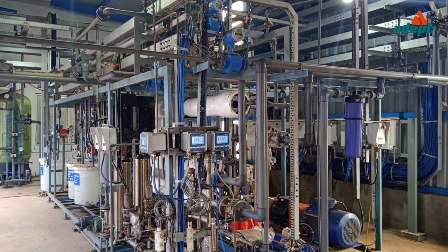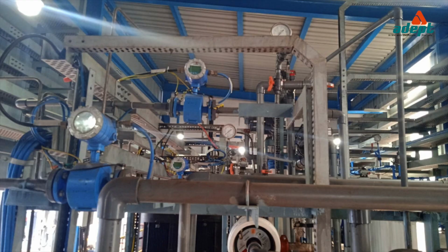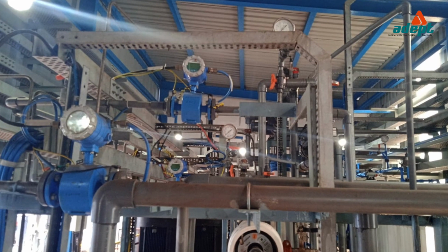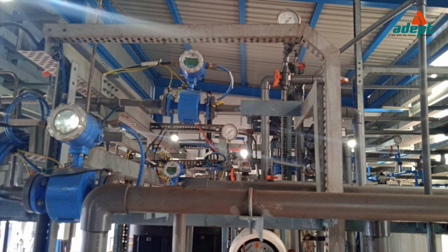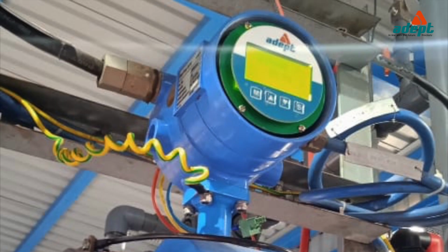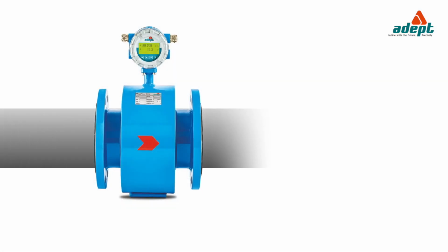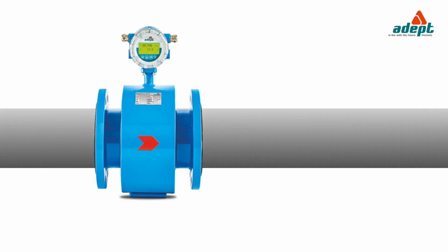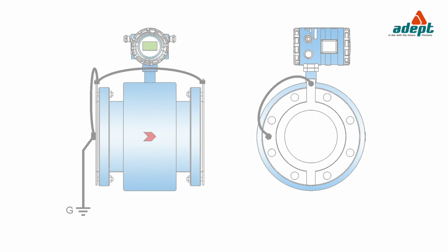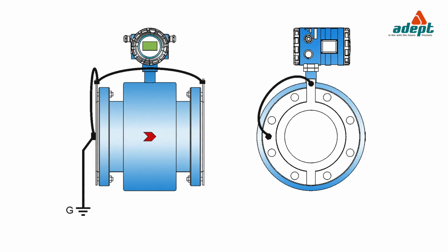Ensure that the installation location is such that water or moisture does not enter the electrical terminations area. If the connecting pipeline is not electrically conducting or is lined with insulating material, strap the grounding rings to the flow tube flanges at either end.